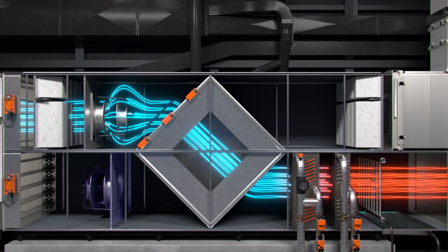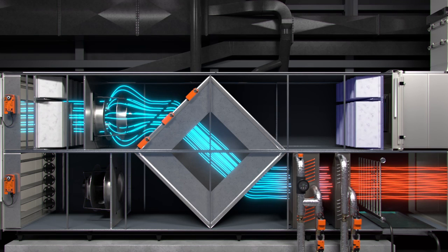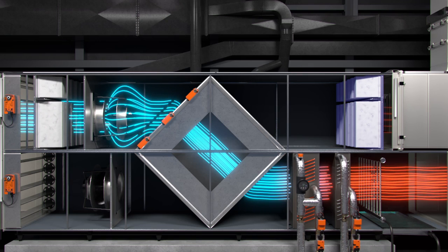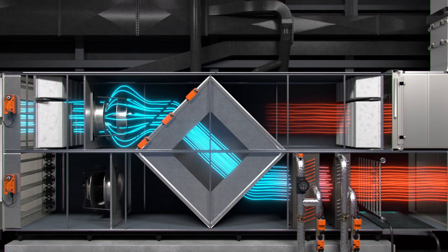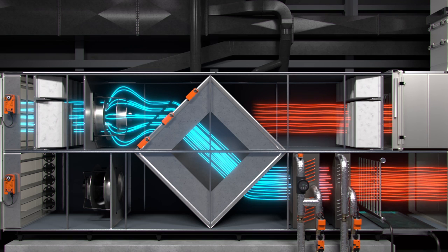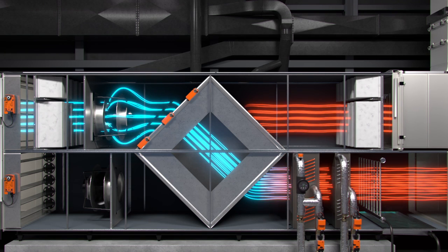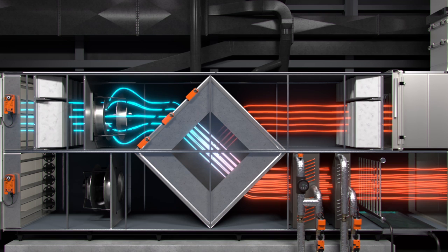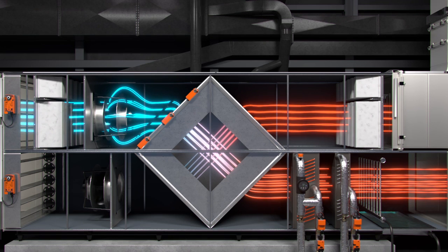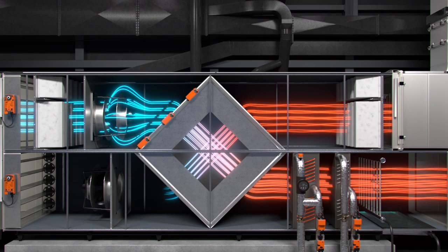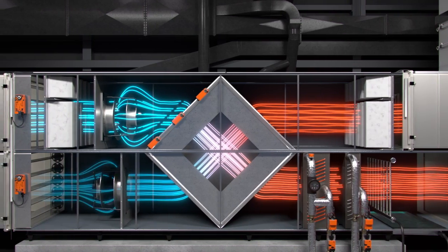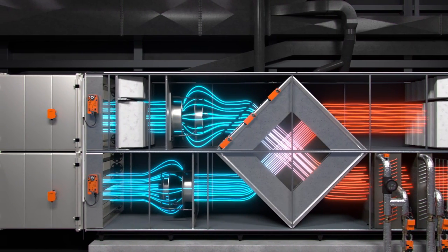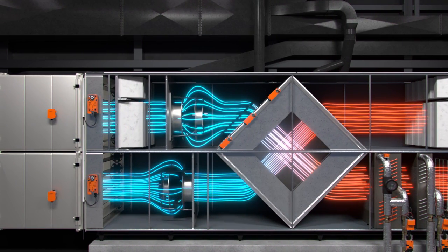air fan. When entering the air handling unit, the extract air is filtered again. This prevents contamination of the air handling unit itself. The extract air then flows through the plate heat exchanger. This transfers the heat from the extract air to the supply air, thus saving valuable energy. Finally, the exhaust air flows out of the air handling unit via the exhaust air damper.